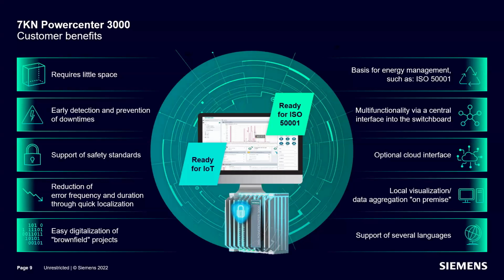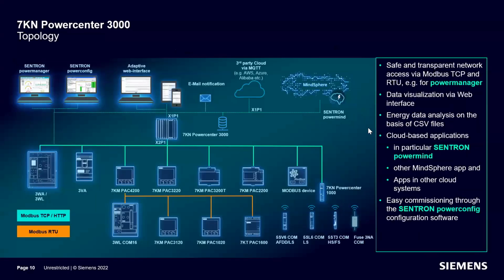As I was talking about the sensors, let me start the pointer. So these are the devices, and this is the gateway, the IoT gateway that connects several devices below it. These are the field sensors, which will be in the panel. Let's say these are the sensors, like the circuit breakers, ACB and MCCB, and metering devices for energy analysis. This will be connected to the Power Center 3000.